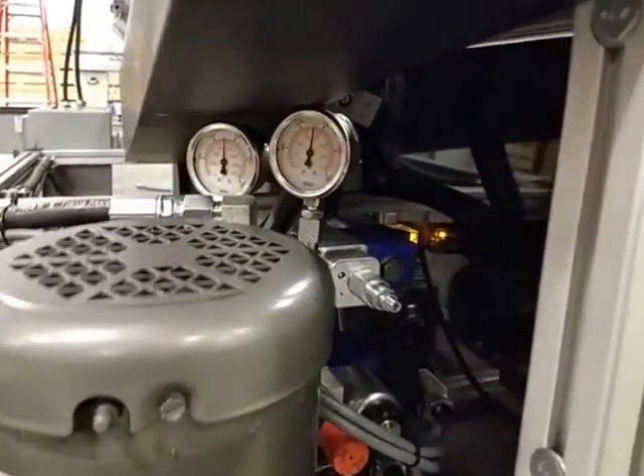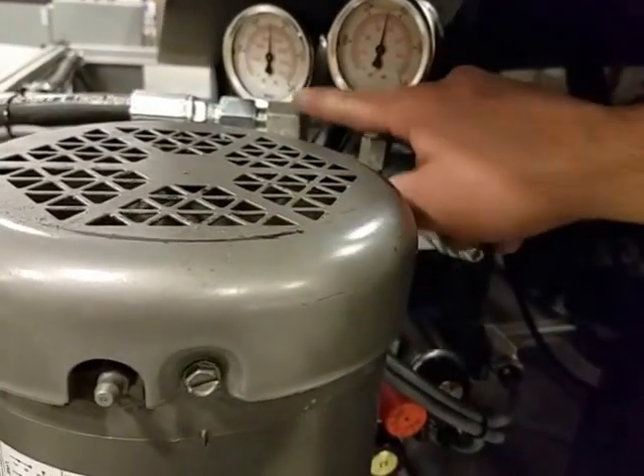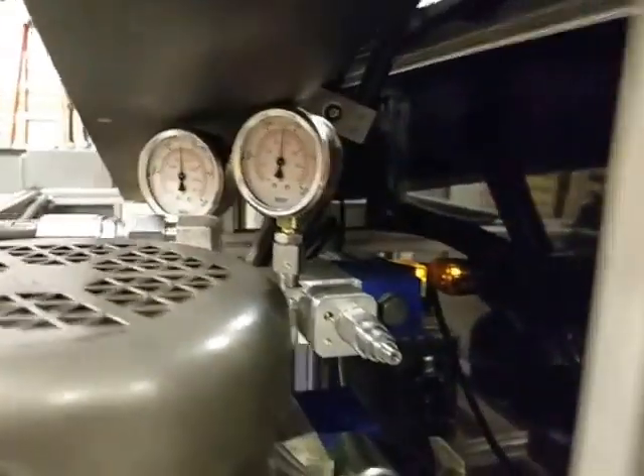So as the accumulator builds pressure, you'll see this gauge max out, and this gauge and that gauge should agree on what pressure we're operating at. The thing that controls the pressure in the system is what's under this little orange cap.